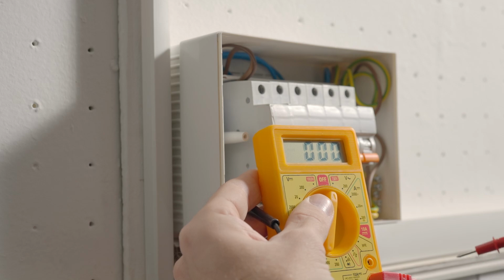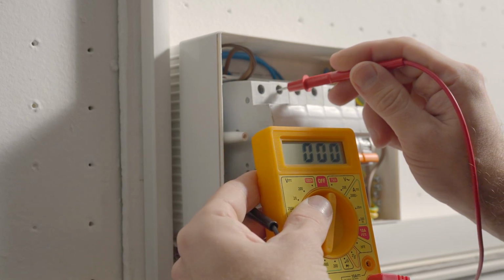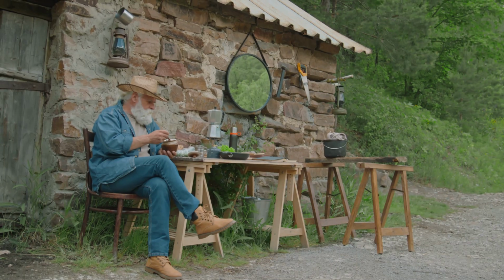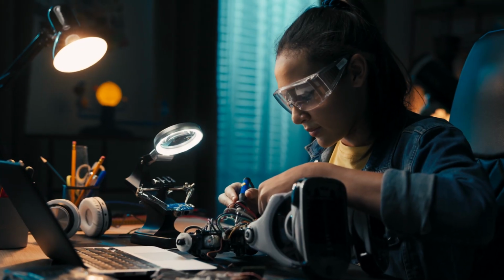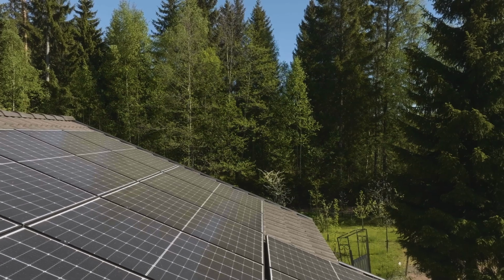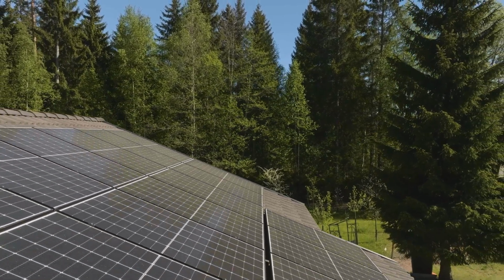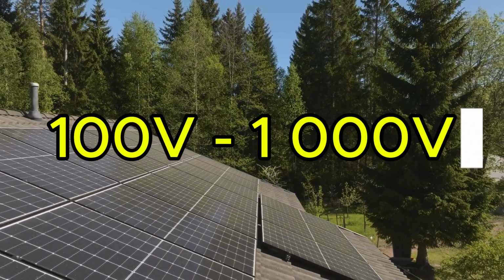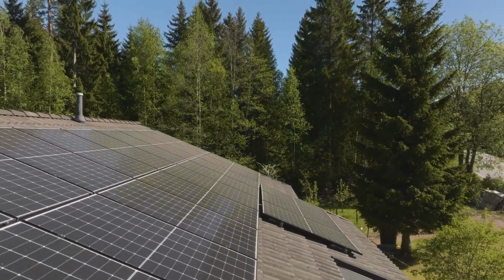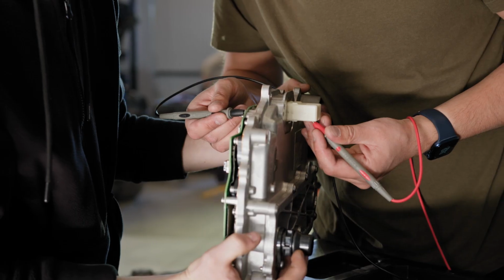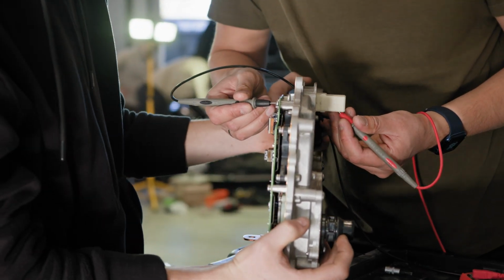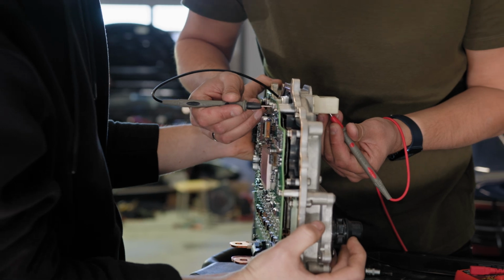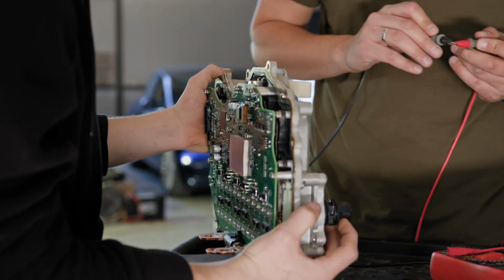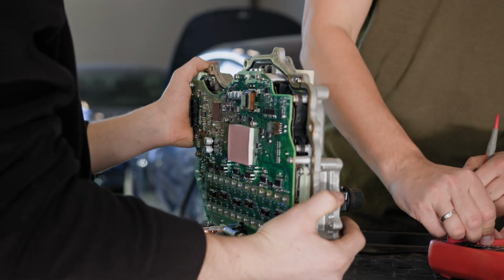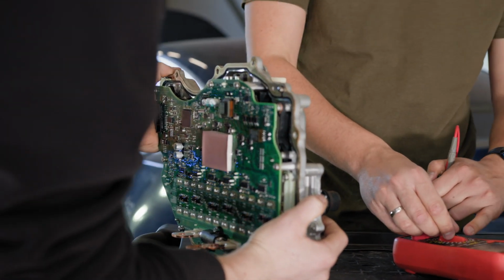Last but not least important thing is the voltage range that the inverter operates on. I will talk a little bit about that later, but you can build your solar circuit in many different ways. Most low power installations operate in a voltage range from 100 to even 1000 volts. My solar circuit will operate in a range from 280 to 380 volts, something like that. There are also a couple of other features that an inverter might have, like 3-phase AC output, parallel mode, many MPPT ports, different communication protocols, safety features, and so on.